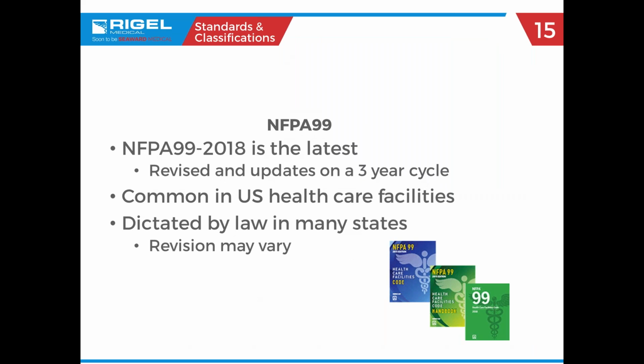Okay, moving on. Here we have the NFPA 99. I'm sure your favorite. These are the most recent standards released. They're typically what I believe most of the facilities and most of the ISOs, at least in the United States, will test to. I know it's not used as frequently internationally, but in the States, this is most likely what you're testing to, I would imagine. They are updated every 3 years, and the last revision was 2018, so look to possibly see some changes in 2021. Sorry, I had to do the math real quick.